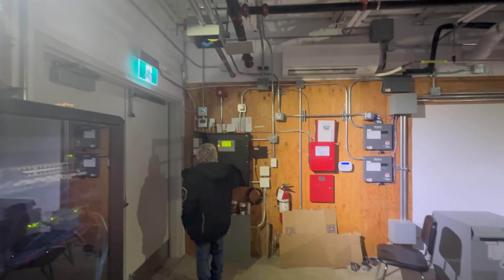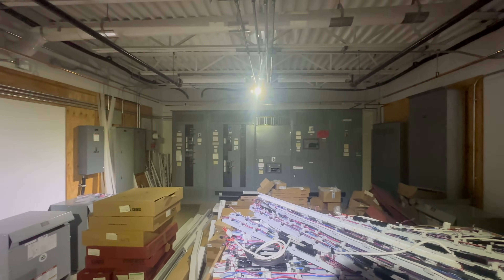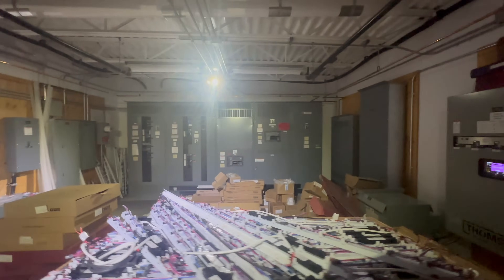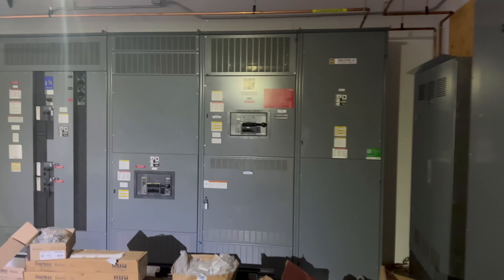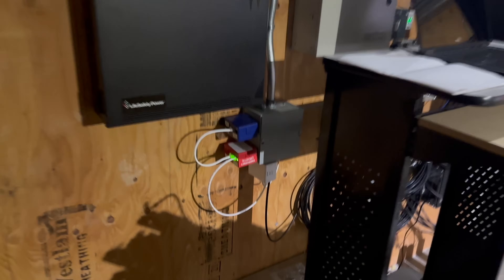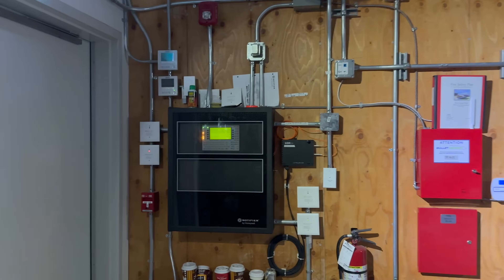So we have a power outage here at these two new schools. Generator is running. Utility power is gone, which also shuts off the solar power because it can't be synchronized with the generator's supply. Lighting control is all switched over to emergency mode as far as what does have emergency source.